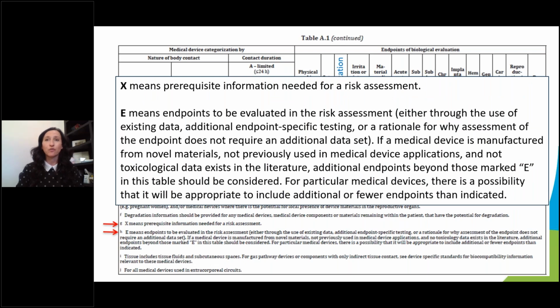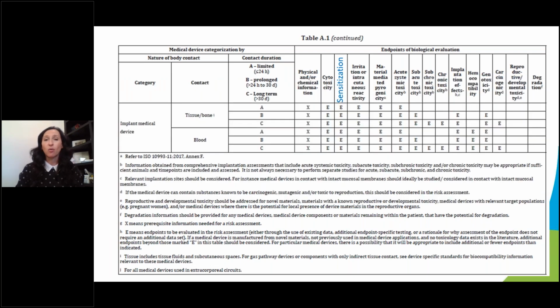And then E is for evaluate. So I've put this on here for your reference for after the fact, but this is straight from the standard. When we think about evaluate, that doesn't mean you have to run out and do all of the testing, but it does mean you need to present data for that endpoint. So if you have all three, like cytotoxicity, sensitization, and irritation marked for your device, that's required, then we need to present data and proof that the device is not cytotoxic, a sensitizer, or an irritant. And we can do that in many ways, and we'll talk about some options for that as well.